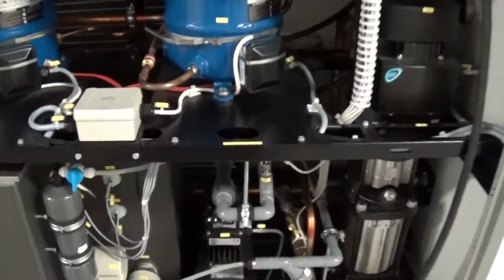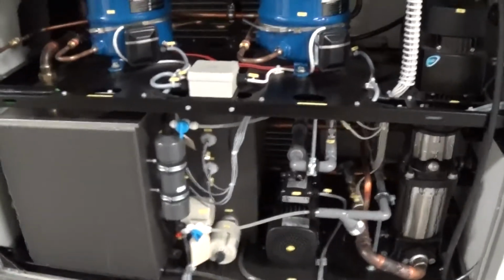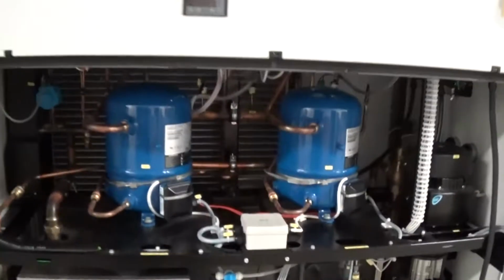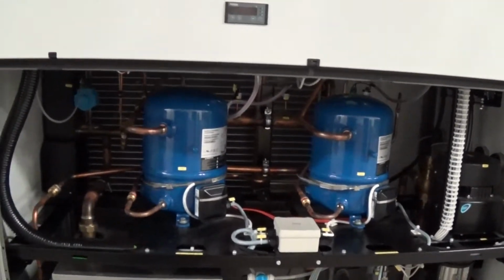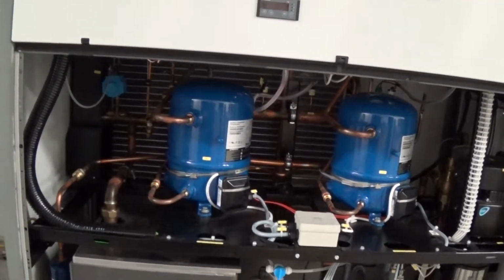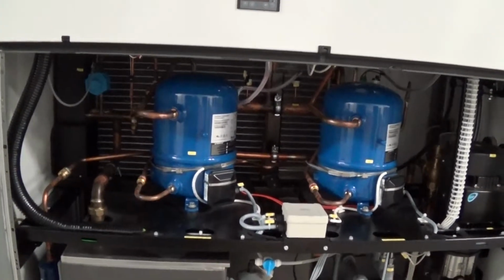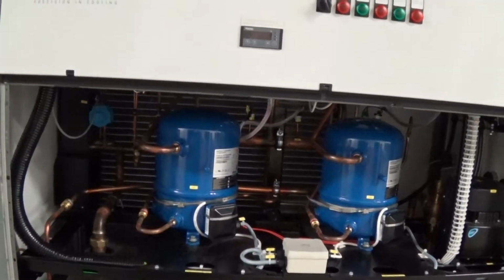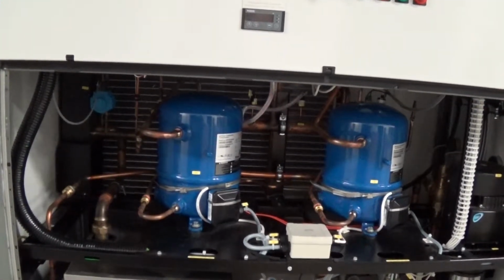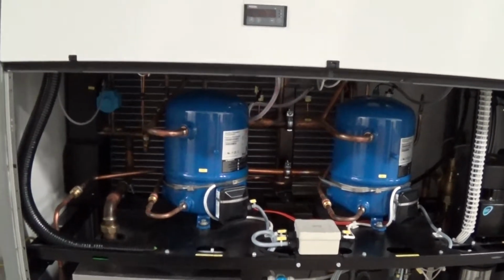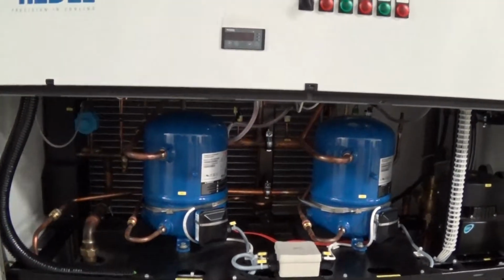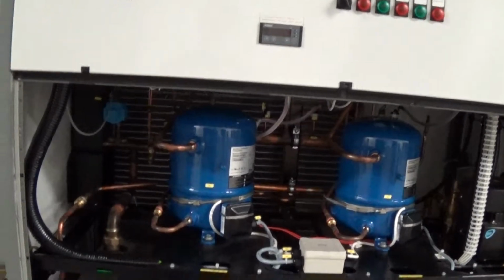Example of a high pressure alarm condition is if it just gets too hot in the building, which is highly unlikely with this type of configuration. It's a pretty healthy sized condenser coil, and I think they were rated for well above 100 F ambient temperatures. Or if your condenser coil's got dirty or something of that nature.